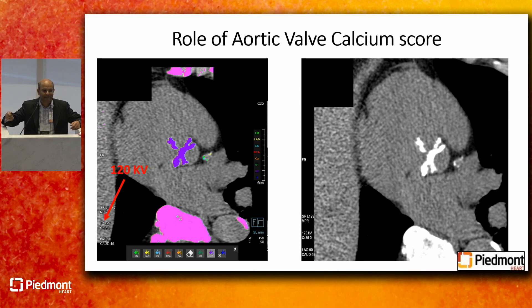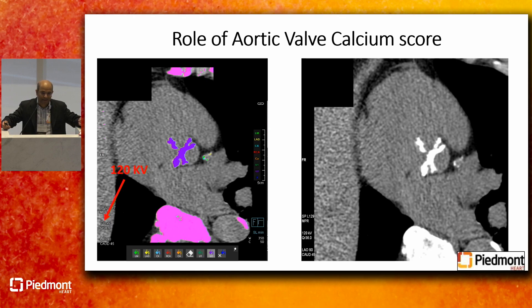Regarding the role of aortic valve calcium score: the Agatston score has been around for a long time. There is a specific way of acquiring this image — we acquire it at 120 kilovolts. It needs to be a three-millimeter slice to give a correct Agatston score of the valve. Depending on the lab and who acquired the image, they may have acquired it at a lower kV, giving a high score. I can make that calcium score lower by acquiring at 140 kV. So the right acquisition is essential for the calcium score to be valid.